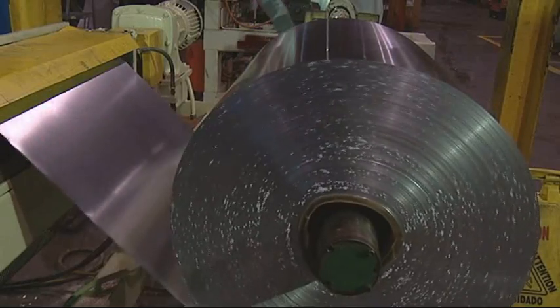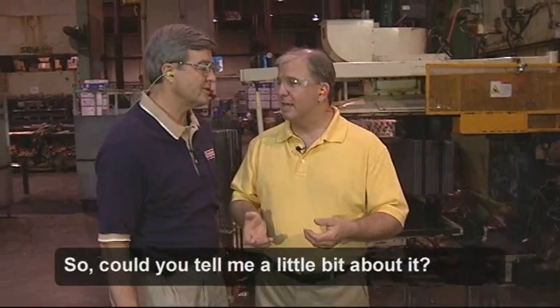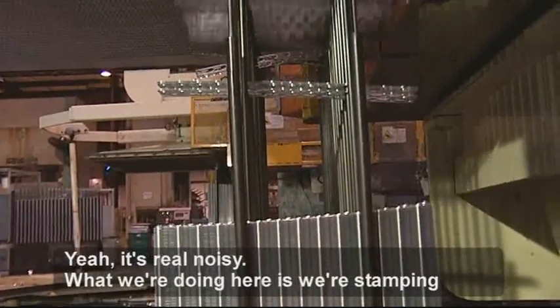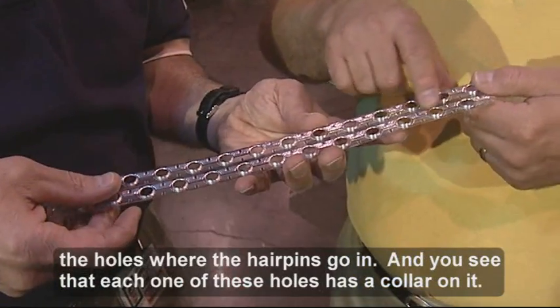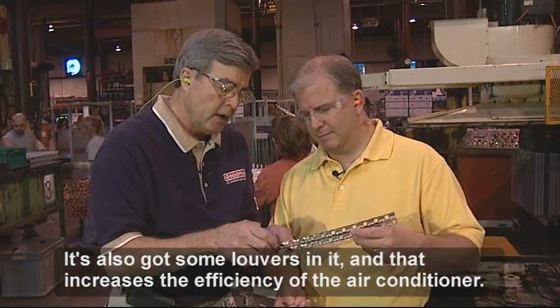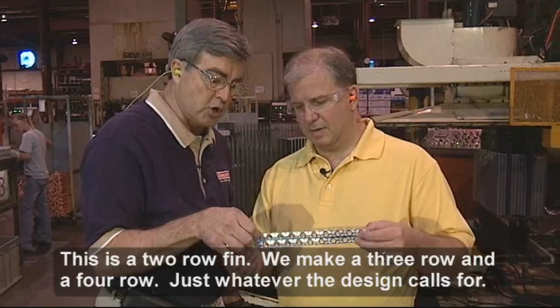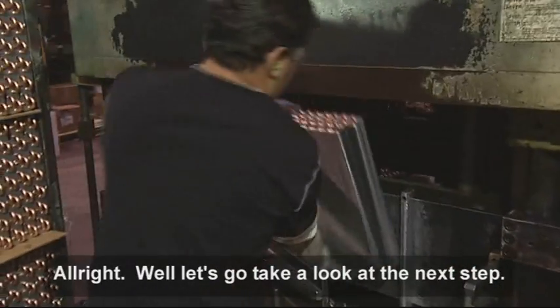The next step is down here where the fin presses are. We've got several fin presses here, and when they're all running it's pretty noisy. What we're doing is we're stamping the holes where the hairpins go in, and you'll see that each one of these holes has a collar on it — that's how it separates the fins so they don't stack right down on top of each other. It's also got some louvers in it, and that increases the efficiency. We make fins that are 14 inches, 18, 20, 24, or 28 inches long. This is a two-row fin, and we also make three-row and four-row — it's whatever the design calls for.